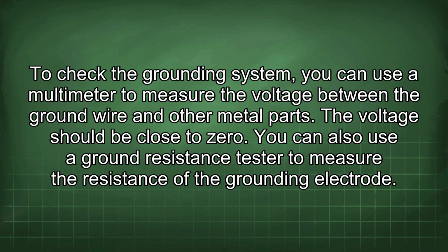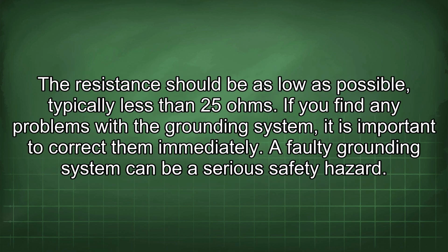You can also use a ground resistance tester to measure the resistance of the grounding electrode. The resistance should be as low as possible, typically less than 25 ohms. If you find any problems with the grounding system, it is important to correct them immediately. A faulty grounding system can be a serious safety hazard.